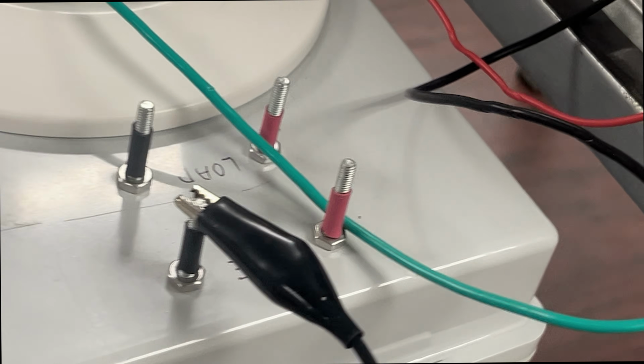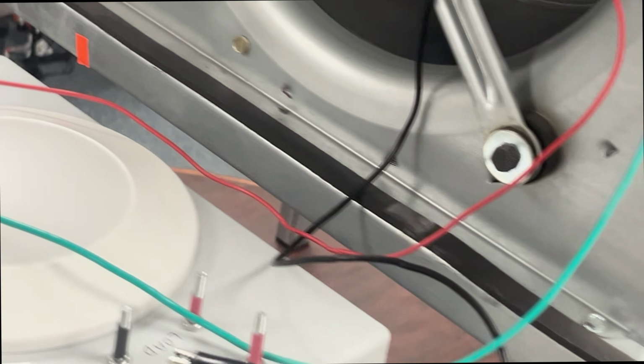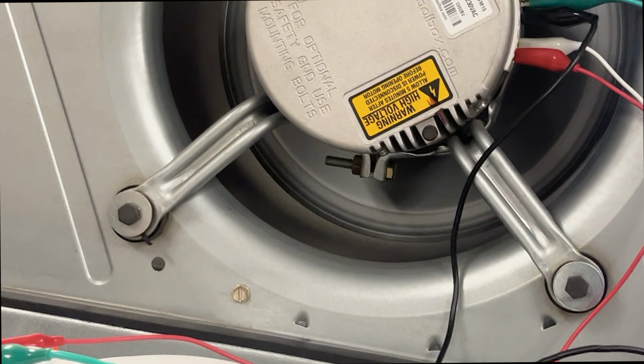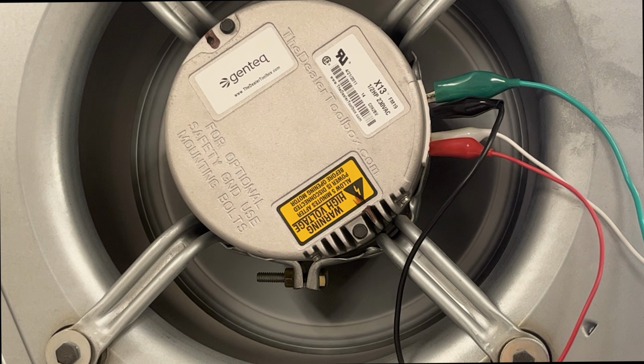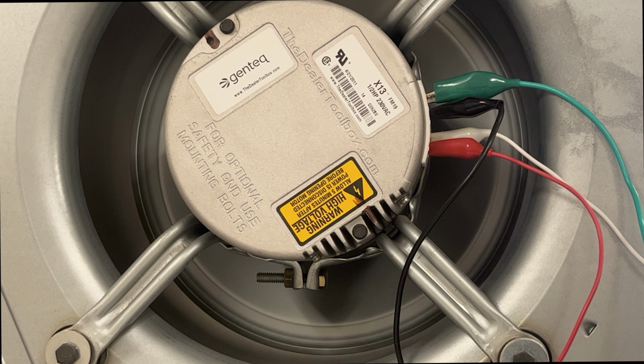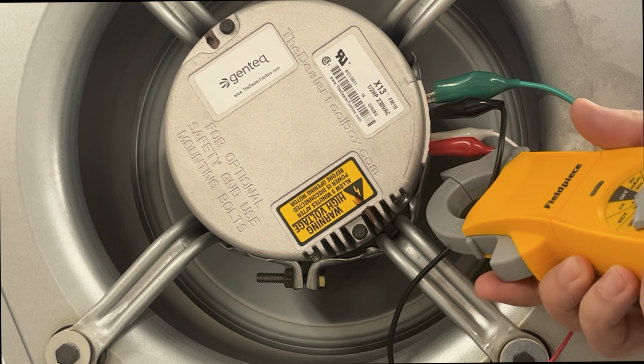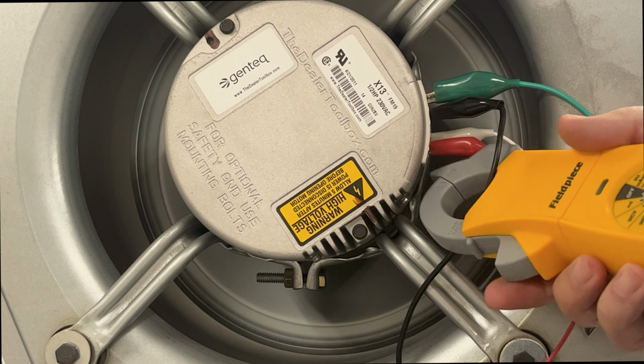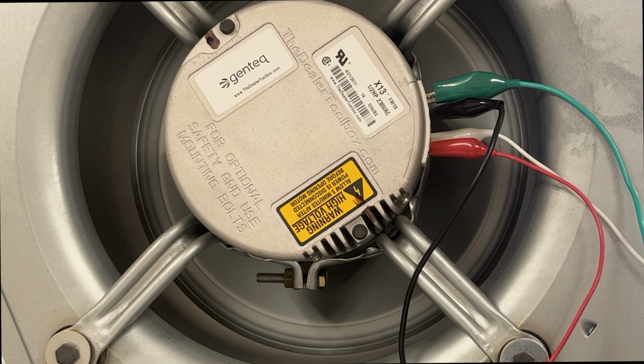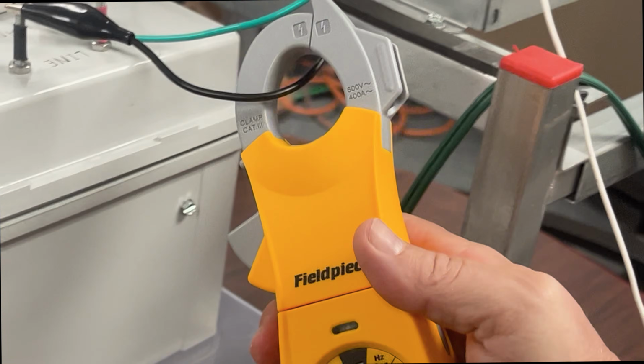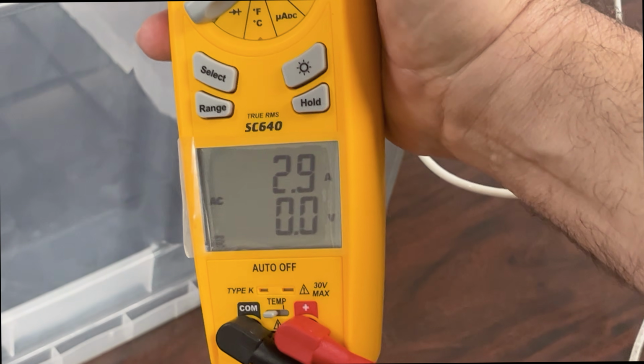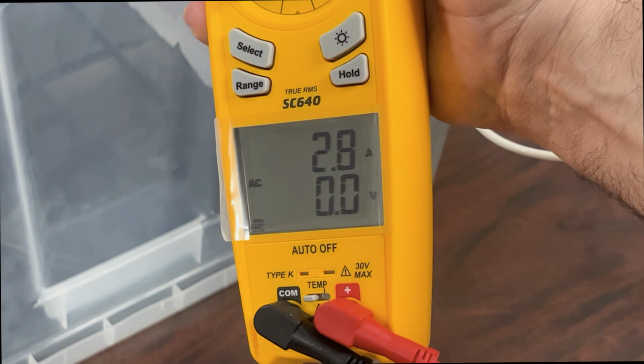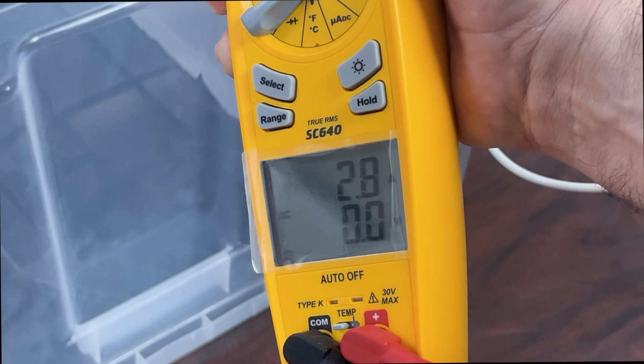That's it. We have one leg of power. 24 volts, E-tap number 5, and then we're just using neutral here. And so I'm going to go ahead and do this again, but we're going to do it with the actual 230, because if I showed you my ampacity here, if I just clamped on this black wire, hopefully you can see that. You do it this way. You can see we're running 2.9 amps. And so that's going to be a lot less than that if we wind up running this 230 volts. I want to show you that difference there.